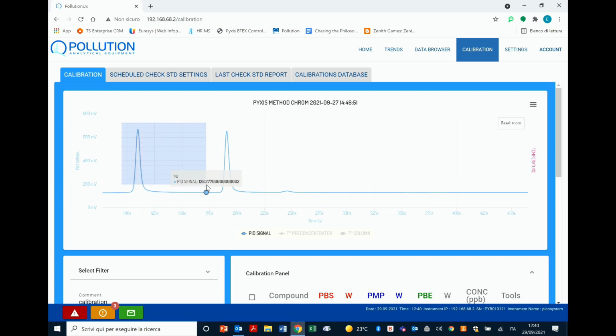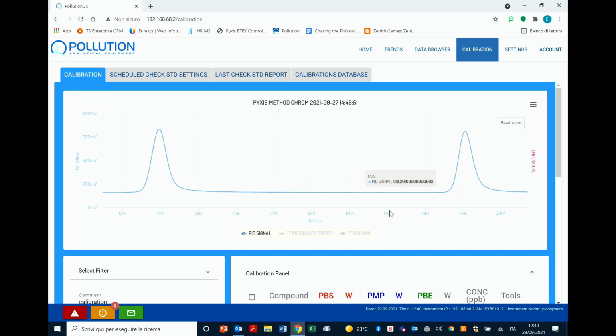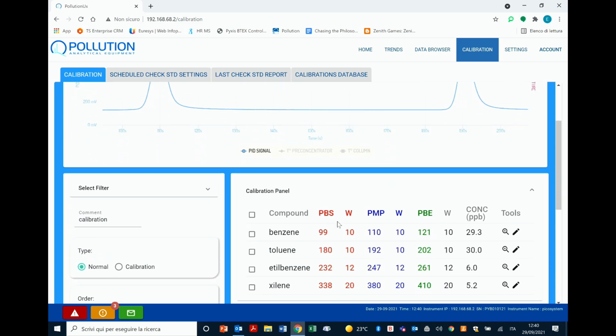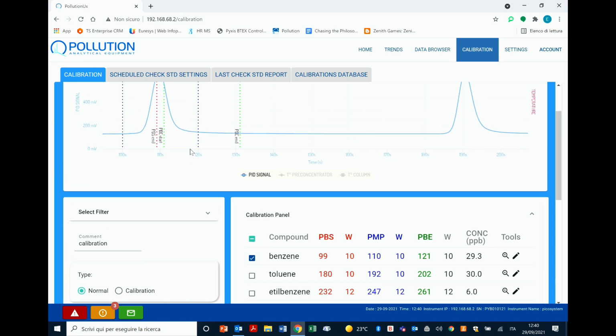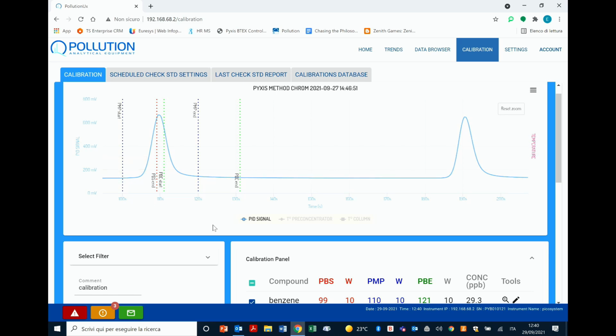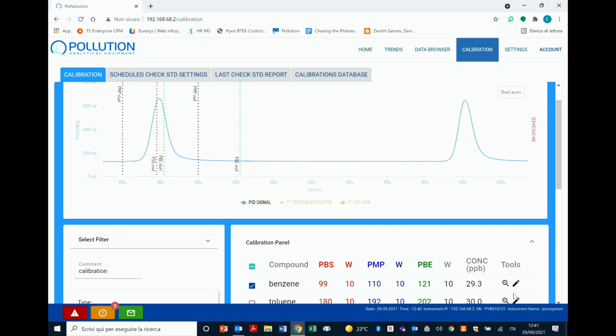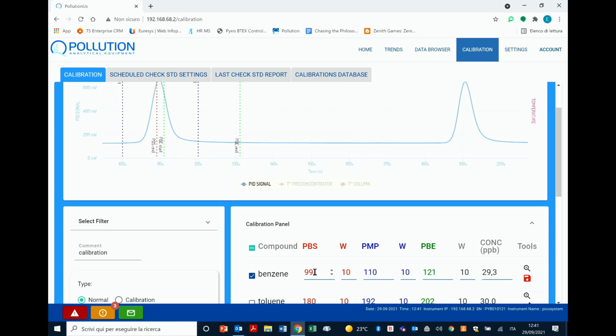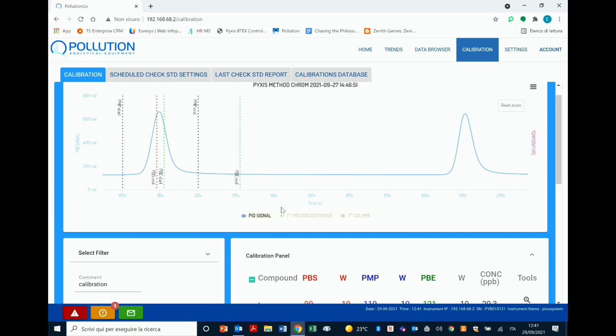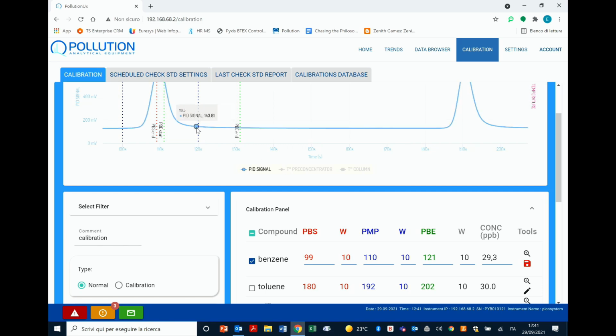So I know that the first peaks are of benzene and toluene. And so you can, here at the bottom, choose which compound you need to calibrate. So for example, if I want to choose benzene, you will see here that this dotted line appears. And you can change the retention time by pressing the pencil icon, so that you can edit basically the PBS, which is the peak base start, and its width. The PMP, which is the peak maximum position, so basically where the peak is positioned. And you can see here the blue dot that starts here and ended there. And the PBE, which is the peak base end, so where the gradient becomes 0 and the curve of the chromatogram peaks get to the bottom line.